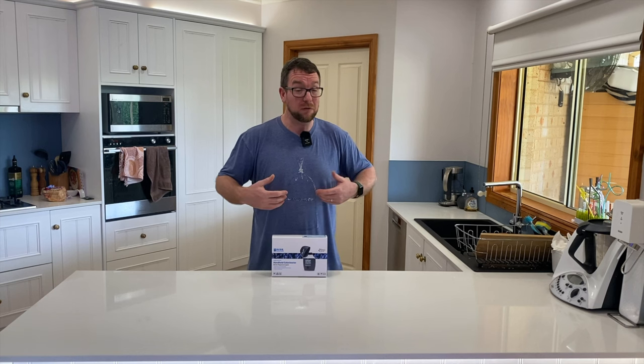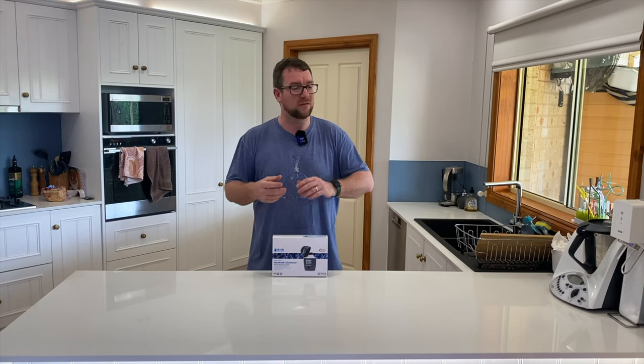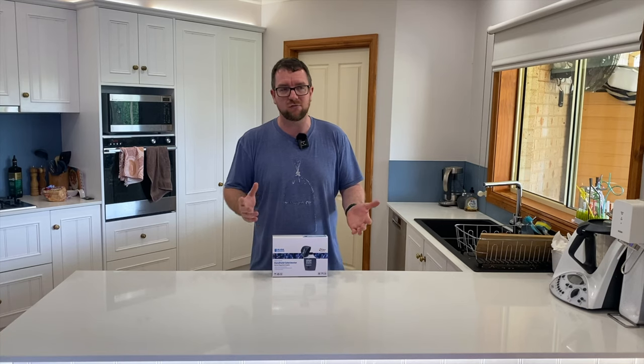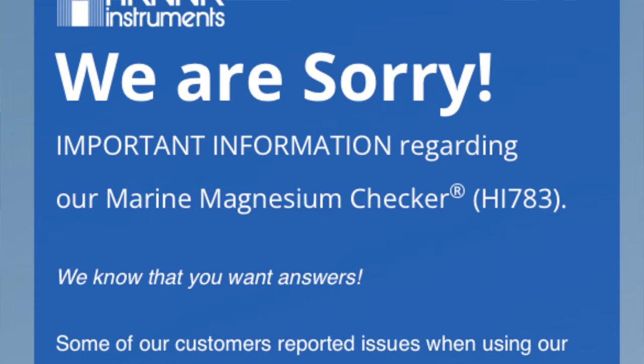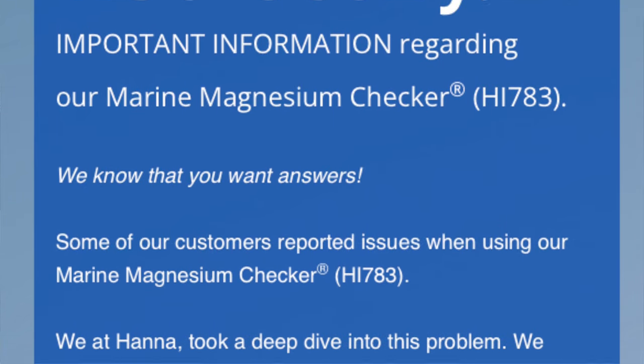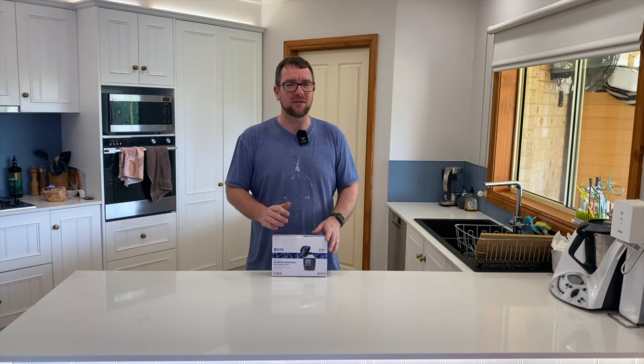The response from Hanna, some people thought it was fantastic. Some people, like myself, thought it was a little bit poor in that they sat on it for about a month telling people they weren't doing things right, that they didn't use the tips of the syringe or that they didn't shake it or leave it long enough or the vial was dirty, etc. And then finally went, whoops, we stuffed up. We actually got the reagents wrong and it's going to give you a higher reading. Yeah, we know.